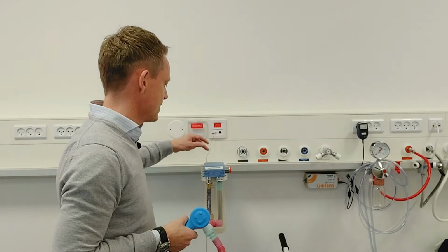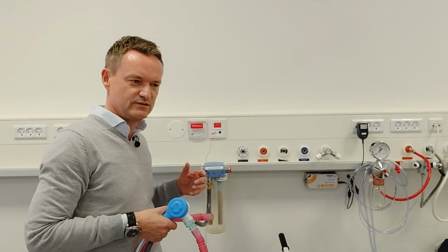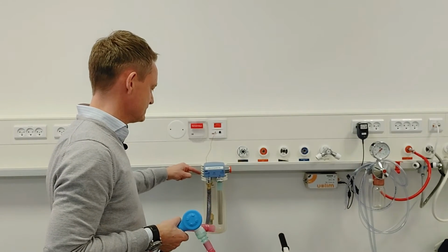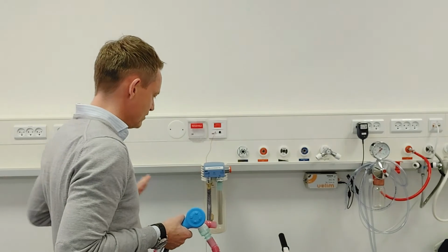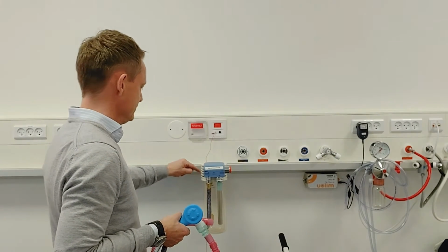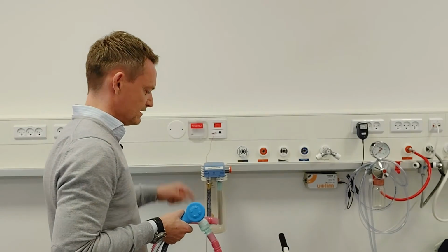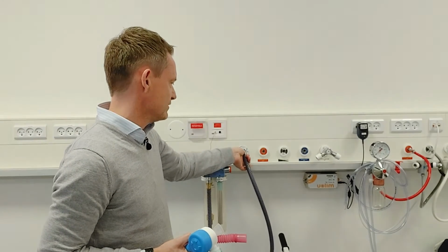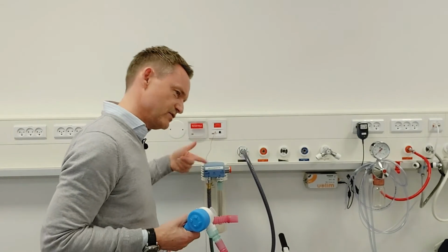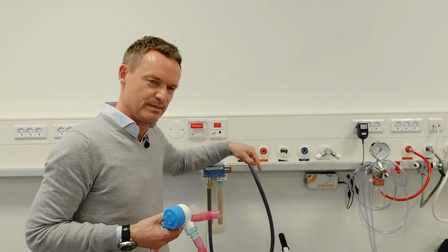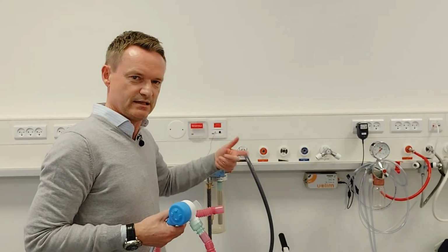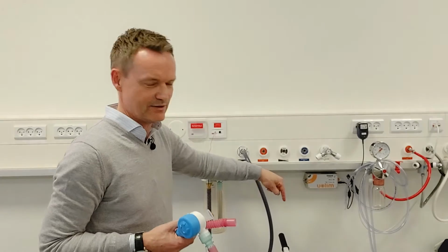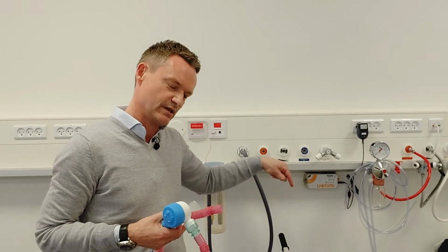It also protects from a high positive pressure. What if the patient all of a sudden blows out extremely heavily? That will not interfere with anything because, as I said before, you have the holes, and if they blow out really heavily into this, it will simply overspill on the side. So, as I said, here's the hose that I plug into my AGSS connection. And what you immediately will hear is that there's a vacuum going on, meaning that the pump down in the basement has started to turn on, and whatever I place into this, it will start to suck in and put it down into the basement where they have a central destruction system in place.